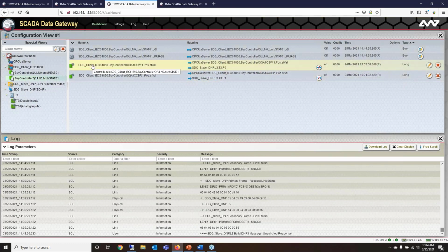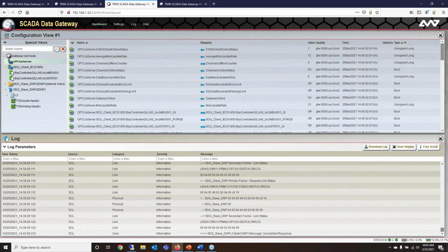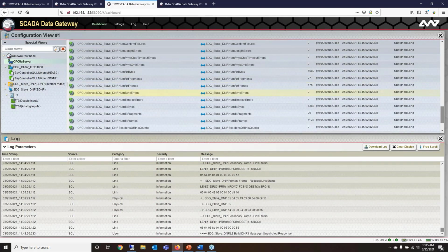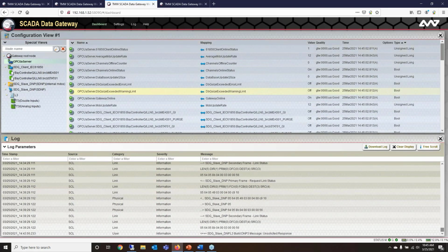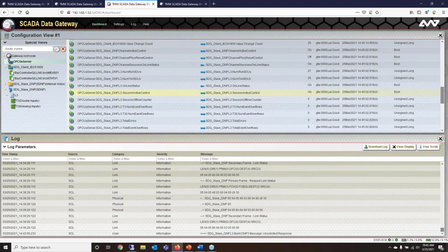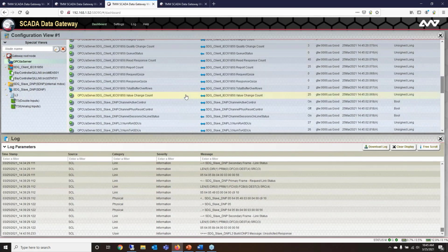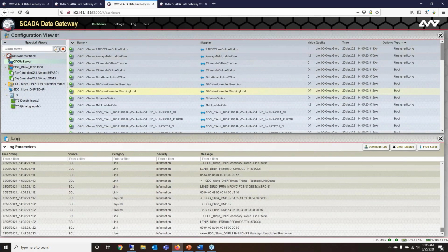And that's something that, if you're licensed for, will happen automatically for you. Anytime you add any data to your SCADA Data Gateway, it's automatically going to be mapped over to this OPC UA server. If I click on it, you'll see all of the data within it displayed out in a table view. This is really nice because it means if you bring up an OPC UA client and connect it to your gateway, you should have access to all of the information inside of your gateway automatically, without needing to configure it, do any CSV file or INI changes, or any mapping. We'll just handle that all for you.